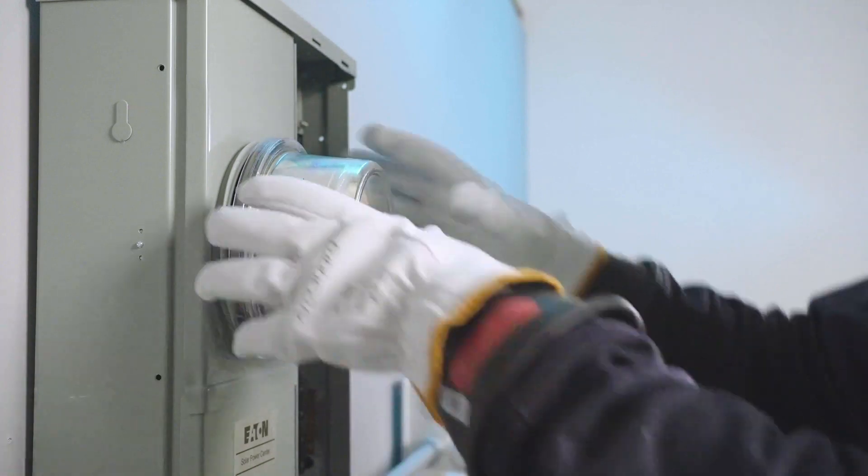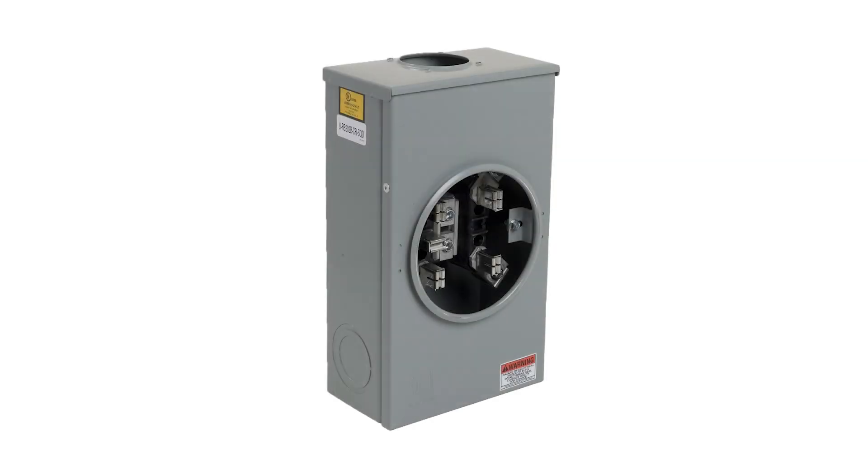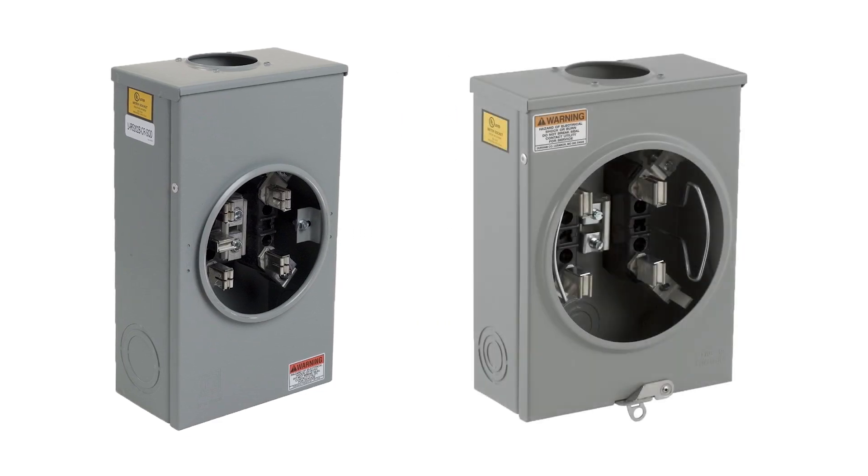Even though the home's circuits have been turned off and are not under load, wiring from the utility provider may still be live. Meter enclosures come in two main variants: ring type, where the meter is secured to the enclosure with a sealing ring, and ringless, where the meter sits behind the front cover.